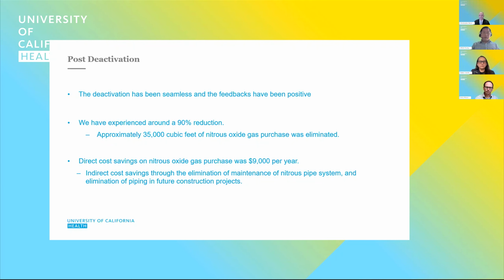So the direct cost savings of not purchasing the nitrous oxide gas cylinders was $9,000 per year. And there are additional savings from emission reduction and so on. And I can imagine there are maintenance costs to the nitrous oxide pipe system which would be reduced because of the deactivation. And lastly, for the two new facilities that we are building at our site, we are not having a nitrous oxide pipe system designed or built in. So in other words, the new sites will not have this.